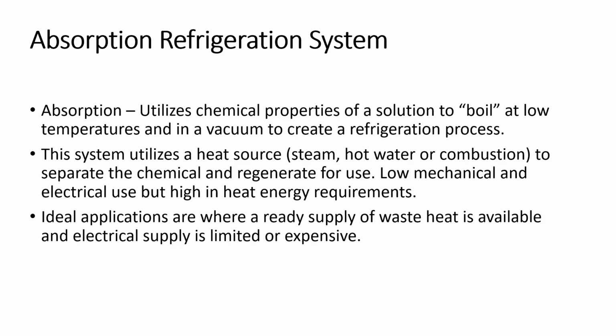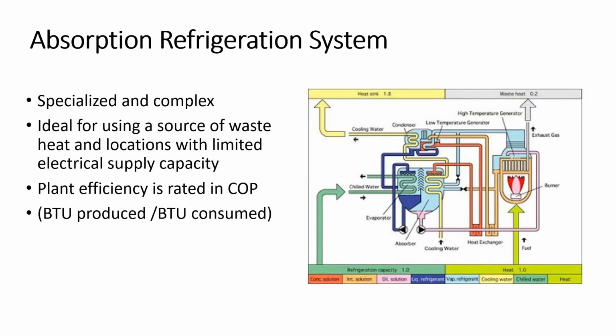These are not as popular today because of the cost of generating heat, but they are still around, and we're not going to spend a whole lot of time on them. They're very specialized and complex. They are ideal if you have waste heat and a limited electrical supply, and their plant efficiency is rated in COP, coefficient of performance, where you compare the BTUs produced by the BTUs consumed. And so you want to stay on a positive number, like 3 or a 2.